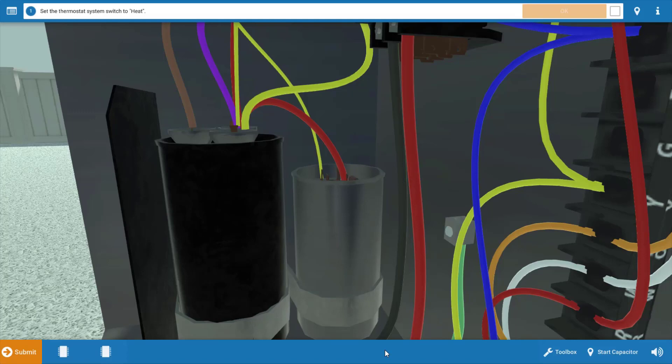And if it's not functioning, the compressor is not going to be able to turn over. It'll try to start on the run winding, but it wouldn't engage the start winding because this capacitor is in series to that.